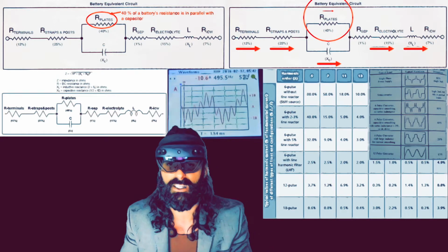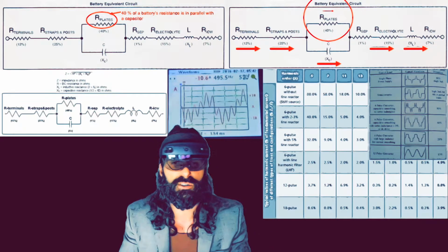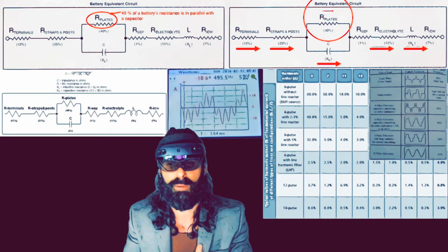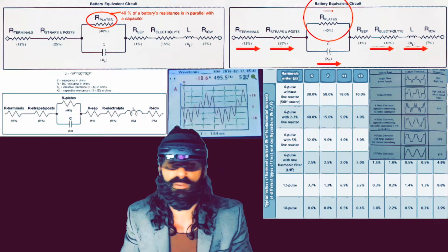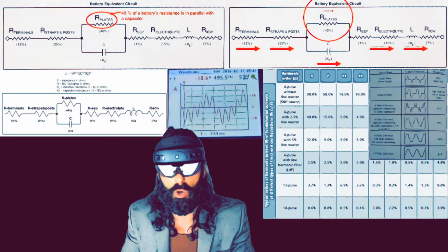But I do come back to spectroscopy, and I still believe that running up to 30 different frequencies and calculating different resistances based on the material science of the battery could provide much more information than simply doing a DC load bank test.